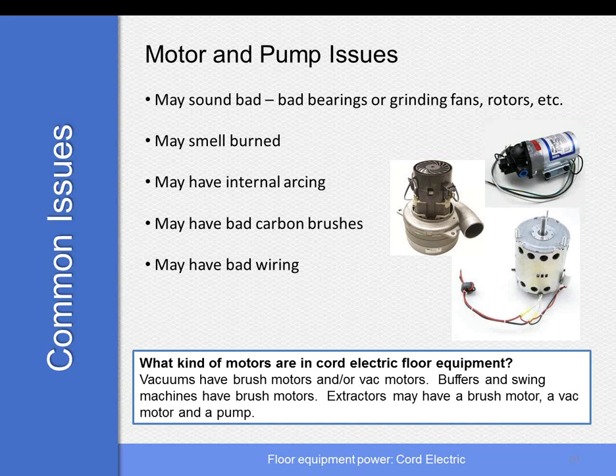Or you'll have a carbon brush that's got chipped or cracked, or that its surface is not smooth, and that'll cause arcing also. That arcing will go away once that carbon brush wears down. And you can also have bad wiring. Well, the leads that run into the motor, they can have their own issues where they have bad crimps, bad solder. Usually that's easier to see, unless it's inside the actual motor casing. That can be a little more difficult to deal with.